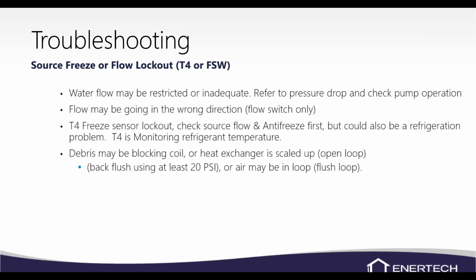You could have debris blocking the coil, or the heat exchanger scaled up on an open loop. You can backflush and clean it out. And again, you could have air in your loop. Make sure you're flushing your loops and make sure your pumps are running. You could obviously be low on refrigerant with that T4 lockout, so make sure we're looking for a leak if you do find it low on refrigerant. You could have a TXV that's restricted or seized. That will give that T4 lockout.